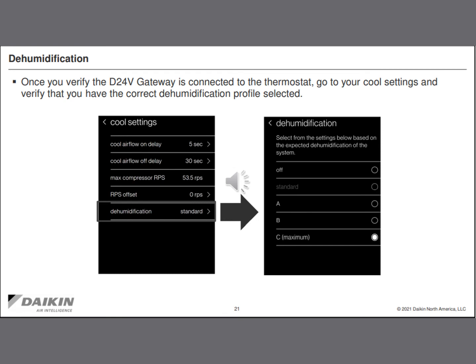And once you've established communication with all of your equipment, it's time to finish up your cool settings. Make sure that you set the dehumidification setting. There are several different profiles there, an A, B, C, or an off, where you can turn the dehumidification profile on or off. For our market here in the Midwest, we're still recommending leaving that dehumidification profile turned off. It just seems to address both our latent and our sensible loads a little bit better for our market. Now, there may be some applications, depending on your equipment size and your load, where this would be helpful, but by and large, we'll want to go ahead and turn this feature off.